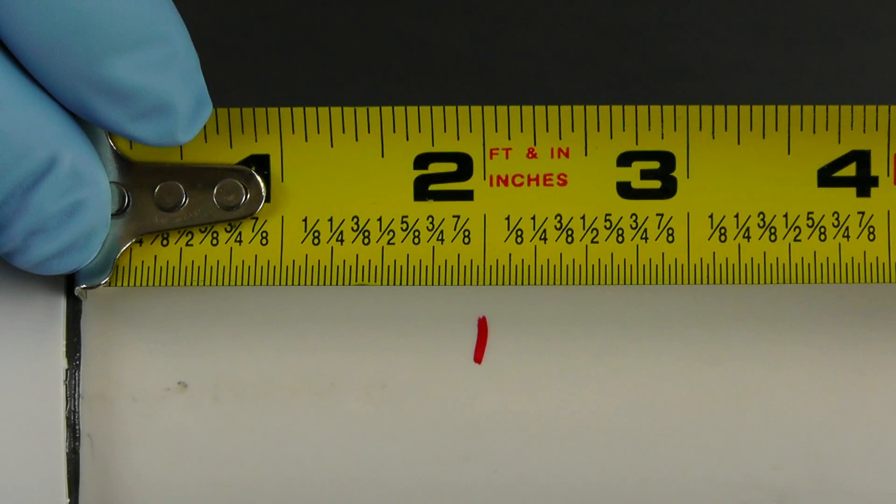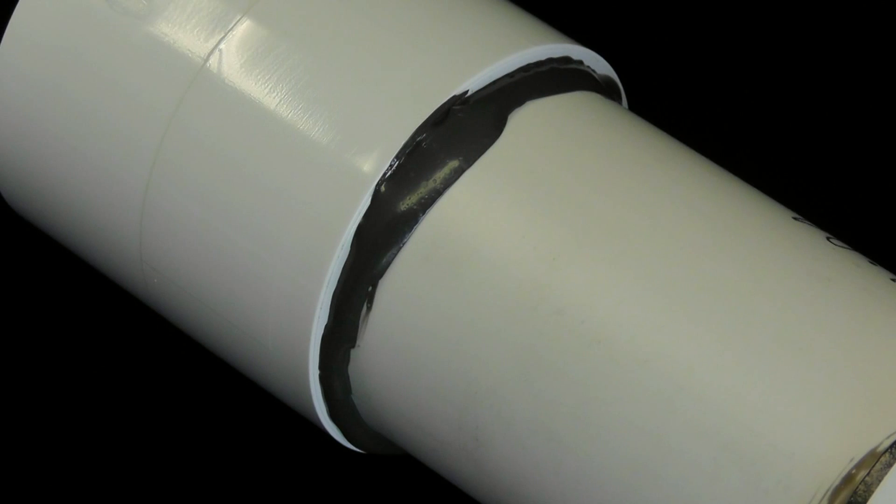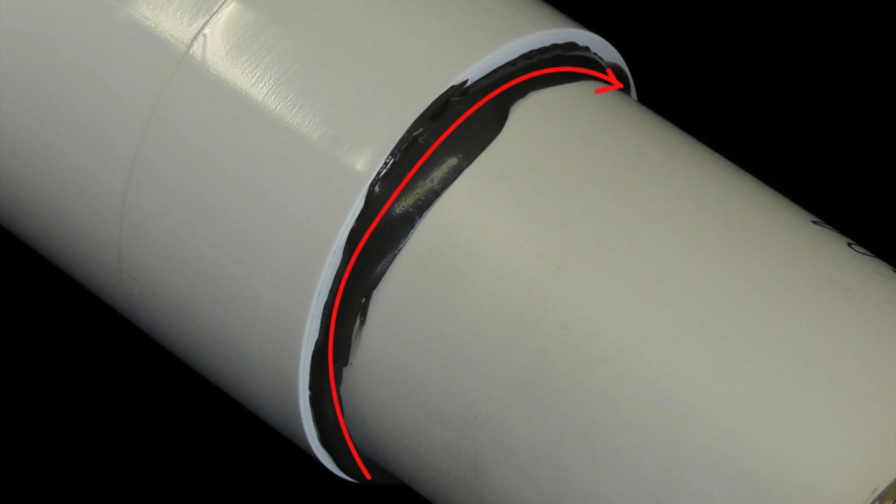Inspect the joint. Measure from the socket entry to the second mark made on the pipe. This distance should be 2 inches which confirms that the pipe is bottomed out inside the fitting. Next, confirm that there is a visible and consistent solvent cement bead between the pipe and socket all the way around the joint. Any visible cement gaps may indicate insufficient cement applied or a light body cement improperly used on a large diameter pipe.